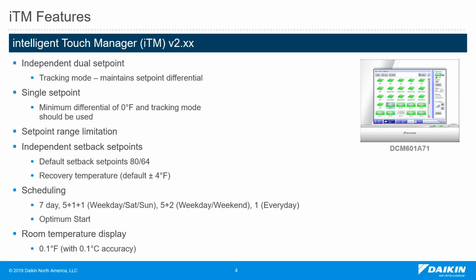More features about the ITM. We support dual set point using tracking mode that can maintain the set point differential. In single set point, we have a minimum differential of 0, and tracking mode can also be used. ITM can also set point range limitation. We do independent setback set point. Recovery temperature for the setback is plus or minus 4 degrees. Some competitors don't have that function. Their recovery temperature is fixed at specific degrees Fahrenheit, but our recovery temperature for the setback is configurable.